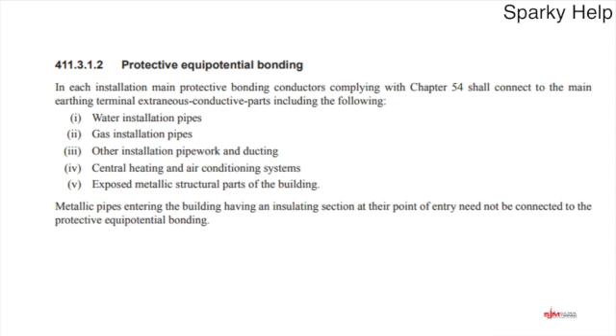Protective equipotential bonding, and it says in each installation, main protective bonding conductors complying with Chapter 54, and that's the sizing of conductors, shall connect to the main earthing terminal extraneous conductive parts including the following. So this is what they list, and it says water pipes, gas pipes, other installation pipework, ducting, central heating, air conditioning, exposed metallic structural parts of the building. But they've got to go to ground.